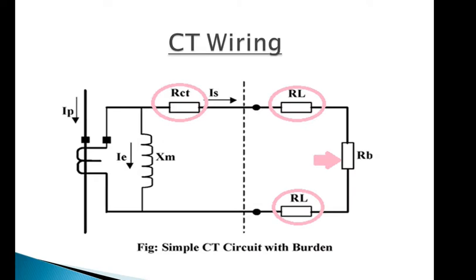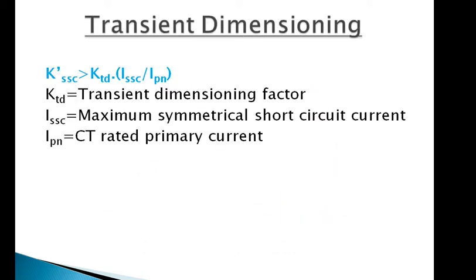From the above IEC equation, we need to calculate the effective symmetrical short circuit factor. Also, we need to check the value of the transient dimensioning factor (K_td) from the CT manufacturer's catalog.